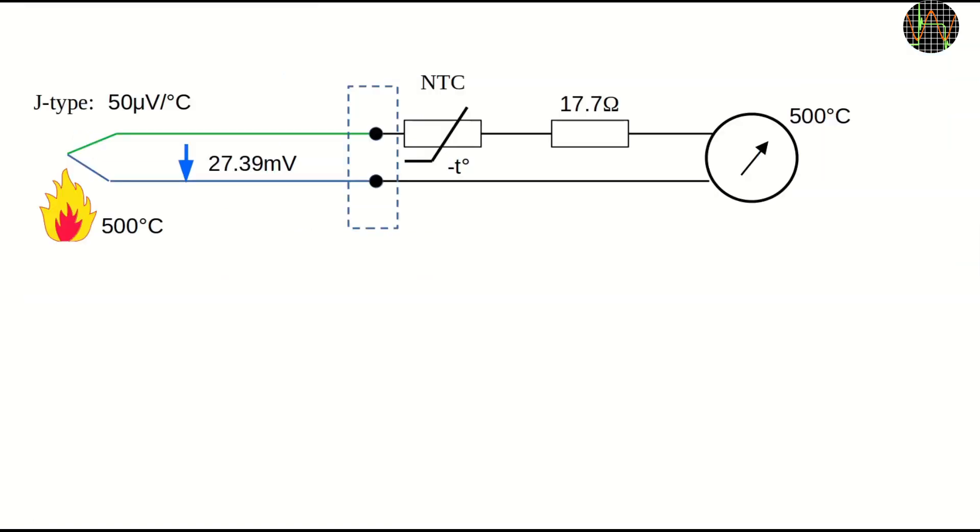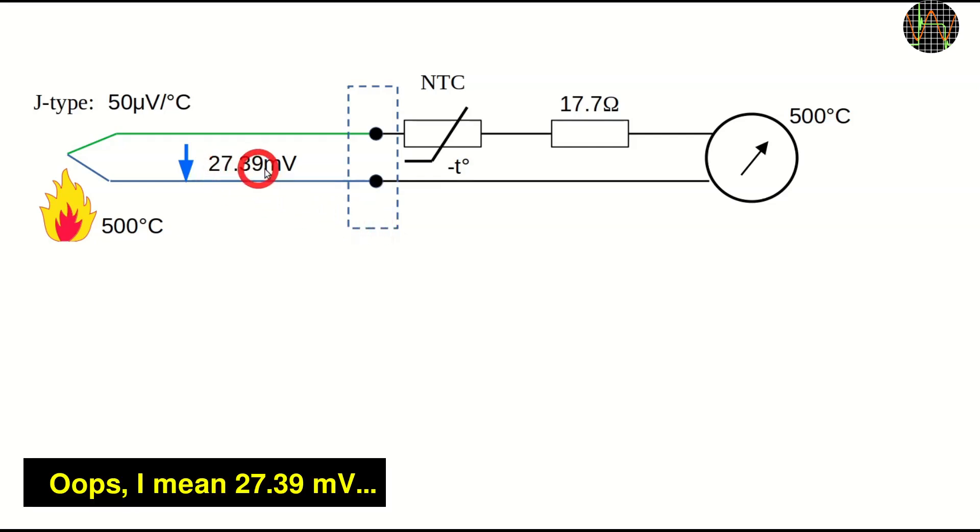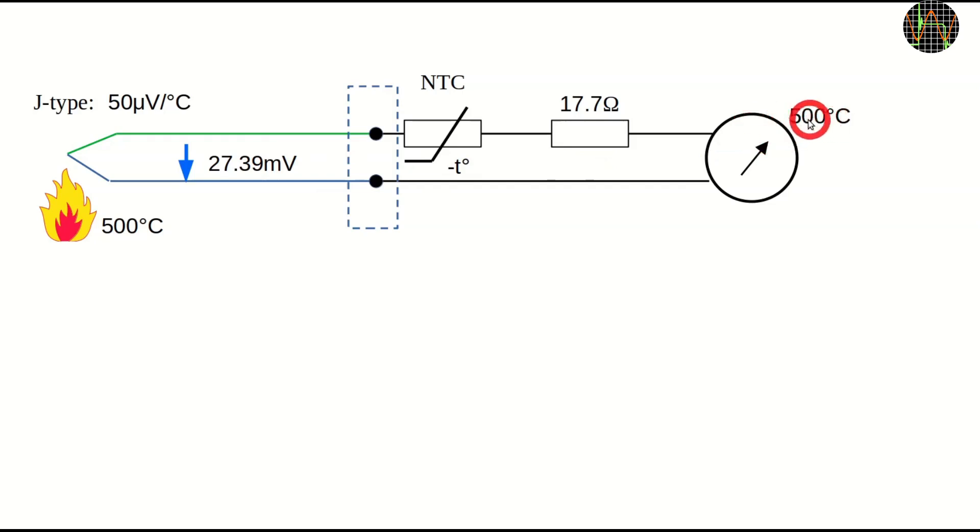The probe would deliver, I guess, 27.39 mV and the instrument would show full scale. If the ambient temperature is higher, like room temperature, the no-longer-so-cold junction would produce a negative voltage so that the overall voltage seen by the instrument is lower, resulting in a lower readout.